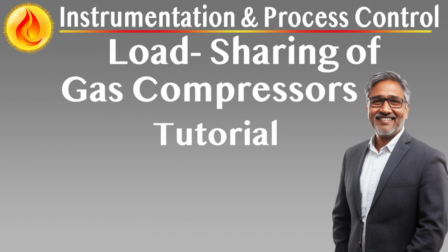Recycle balancing, coordinated valve modulation for uniform surge recovery across compressor trains. Overview. Recycle balancing is a targeted control feature designed to manage the behavior of multiple compressors simultaneously in recycle. In parallel compressor configurations, recycling is sometimes unavoidable, particularly during turn-down, startup, or transient conditions.